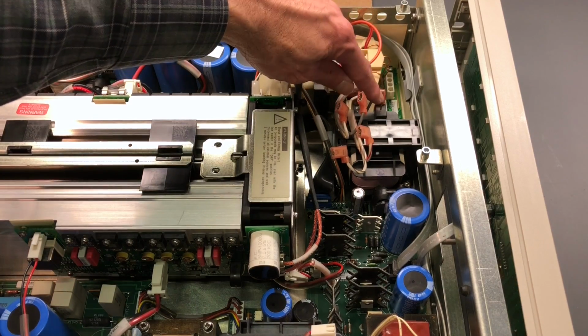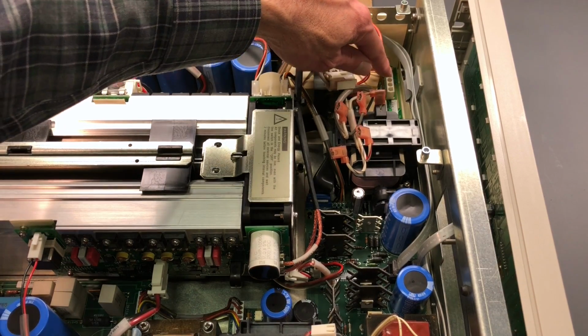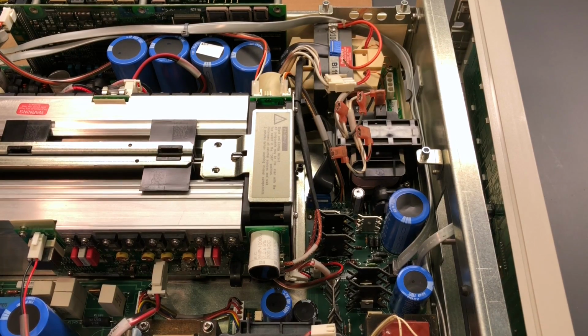It's kind of hidden by this other terminal, but these two connectors have some voltage markings next to them. It's a little bit confusing because on the one connector it says 200 volts and the other connector says 240, so you don't see anything about 120 volts. But it's more of a range selection. So the 200 volt position is used if the input voltage is 100, 200, or 208 volts, and the 240 volt position is used for 120, 230, or 240 volts. So again, it's more of that high-low range, rather than just strictly voltage.